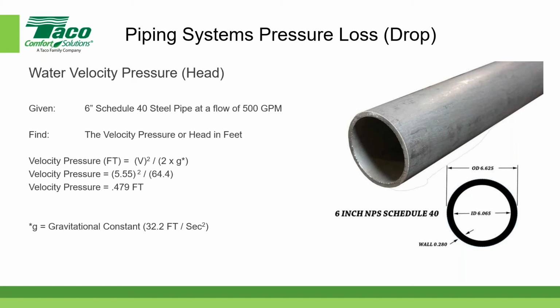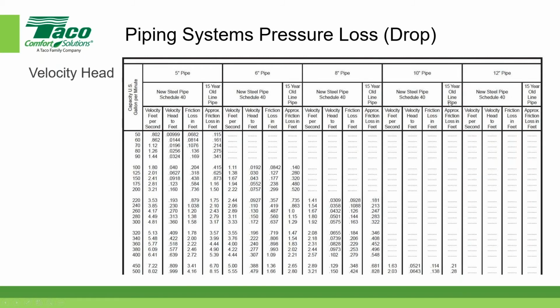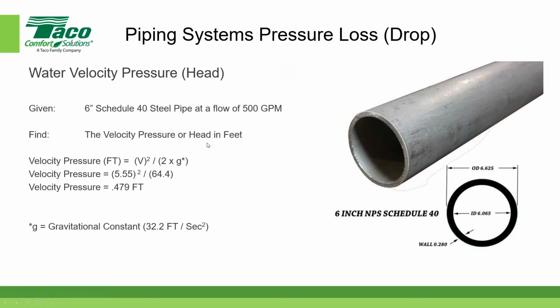Let's now look at that same table that we had a minute ago. We're looking at the same 6-inch schedule 40 steel pipe. Just repeating a couple of things: 500 gallons per minute, and there is the velocity pressure, 0.479 feet, right there. So you can calculate those values or you can look them up in the table. This table is based on the calculation that I showed you on the previous screen. Any questions about velocity head?